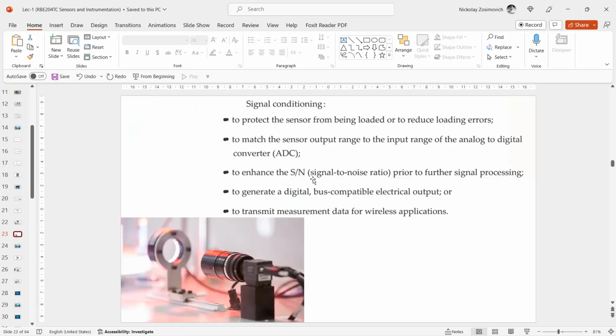Signal conditioning may include: to protect the sensor from being loaded or to reduce loading error, to match the sensor output range to the input range of the analog to digital converter, to enhance the signal to noise ratio prior to further signal processing, to generate a digital bus-compatible electrical output, or to transmit measurement data for wireless applications.